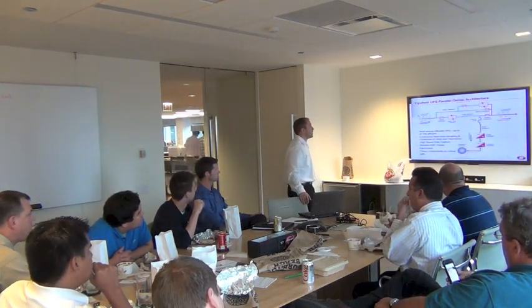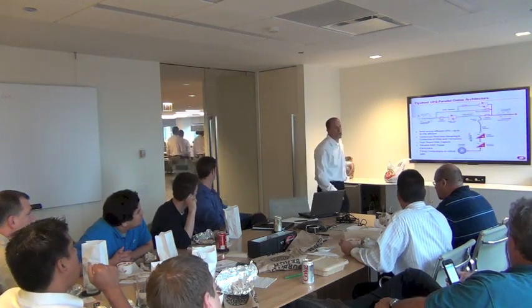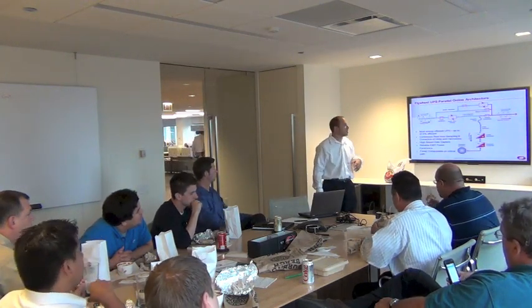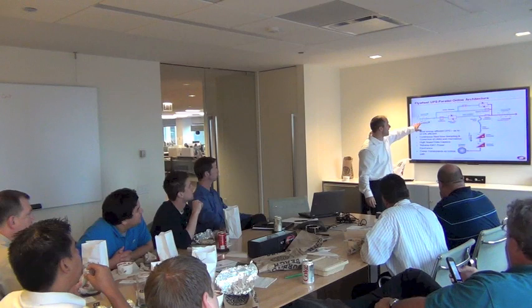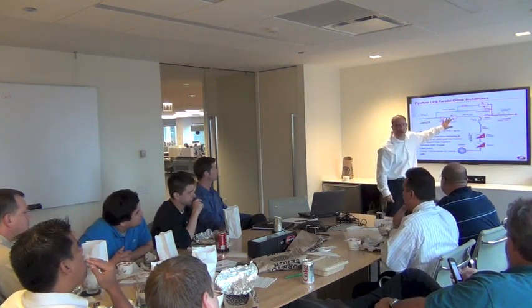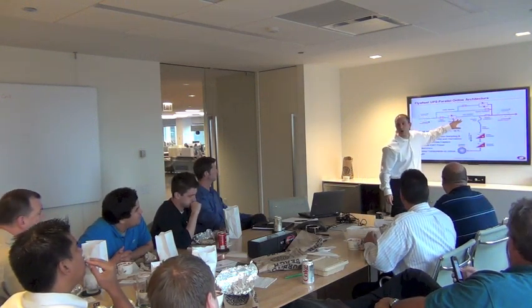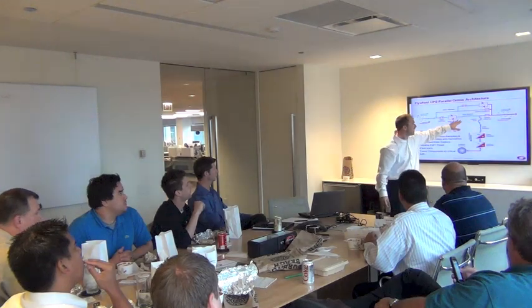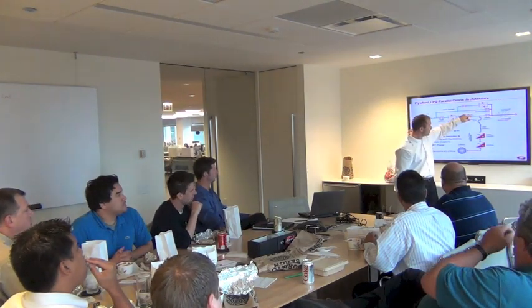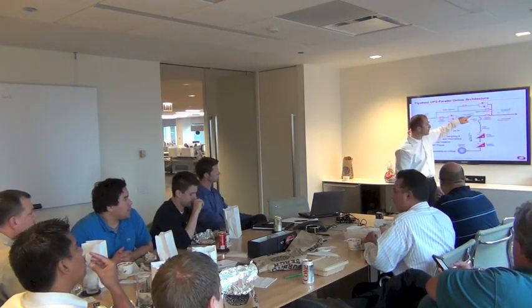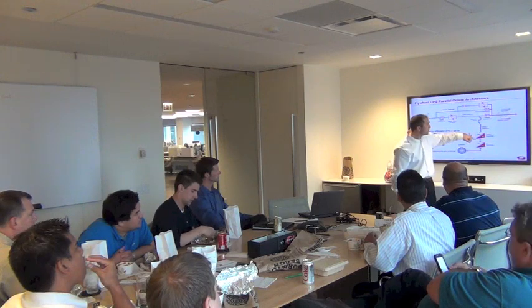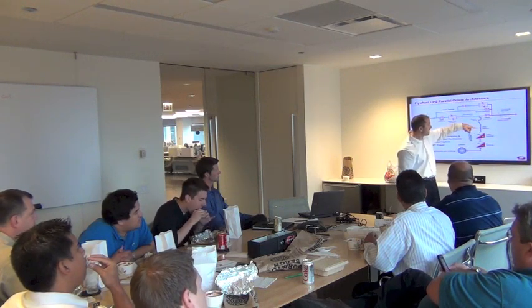So this is a high-level one-line of our topology. We are a parallel online interactive UPS. So we come in AC, we stay AC along the entire critical path. We go through a very large choke in each flywheel cabinet, and we basically circulate all of the reactive currents, all of the harmonic currents across the utility inverter, across the DC bus, and back out to the main.